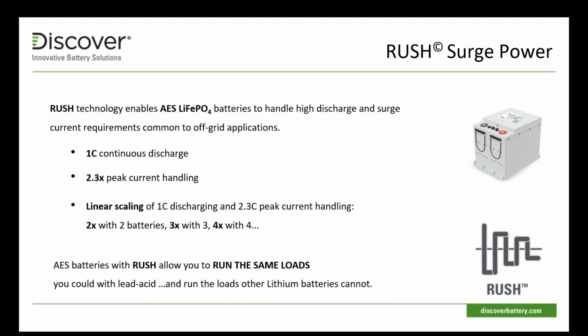Typically, it matches very well on a one-to-one basis for an inverter under 5 kilowatts, and then above 5 kilowatts, we get into some larger systems, and we'll show you a little bit about how to do that coming up. But surge power is a distinguishing feature. There are other lithium battery products on the market, but many of them, the vast majority, cannot handle peak current much more than 1C in some cases, let alone 2.3 times C rate.